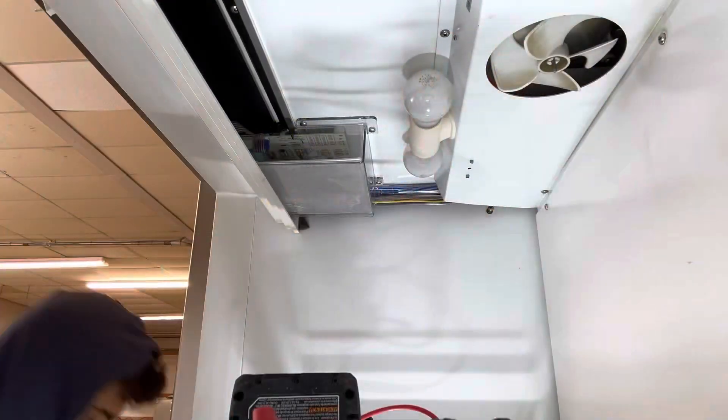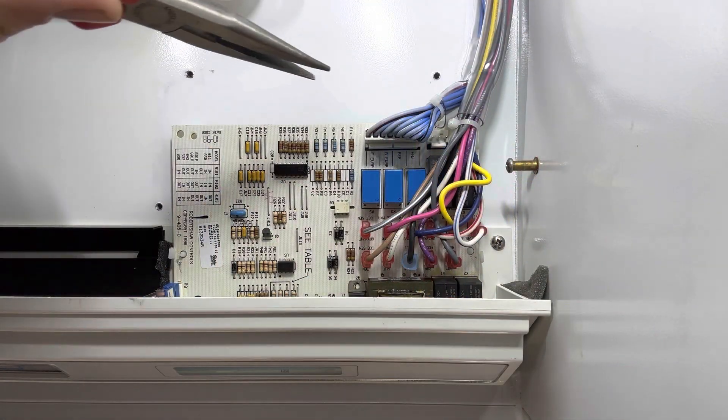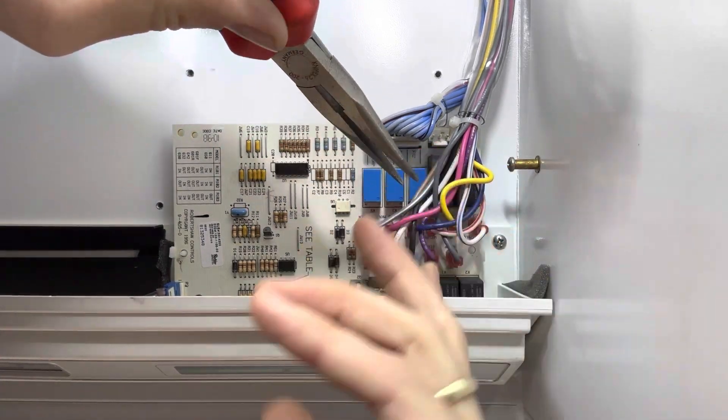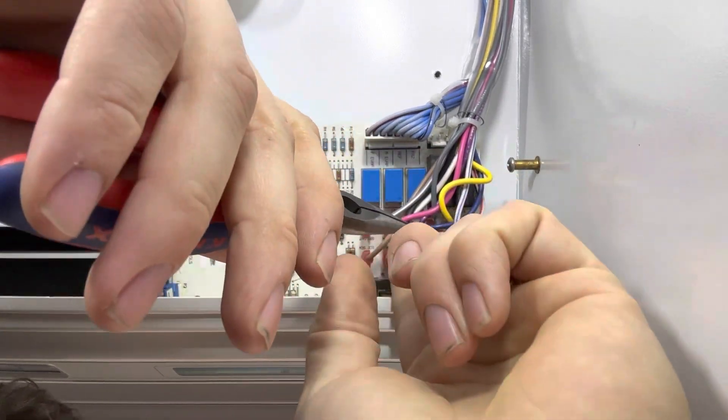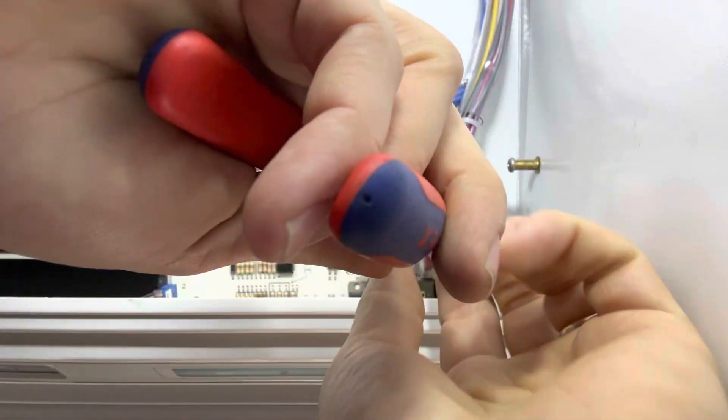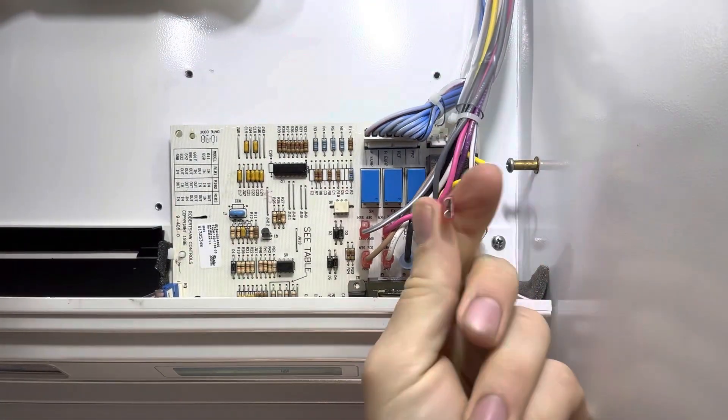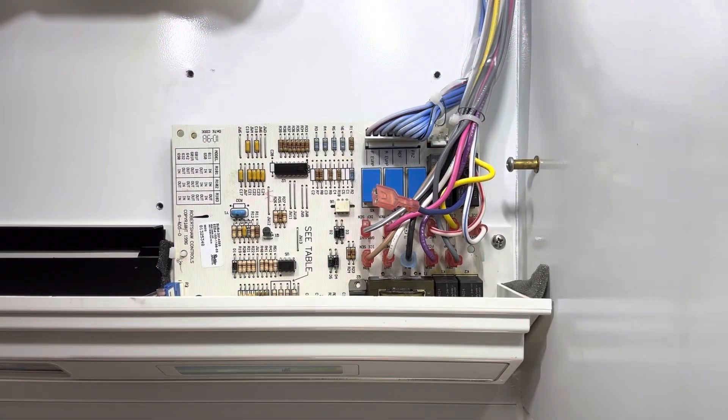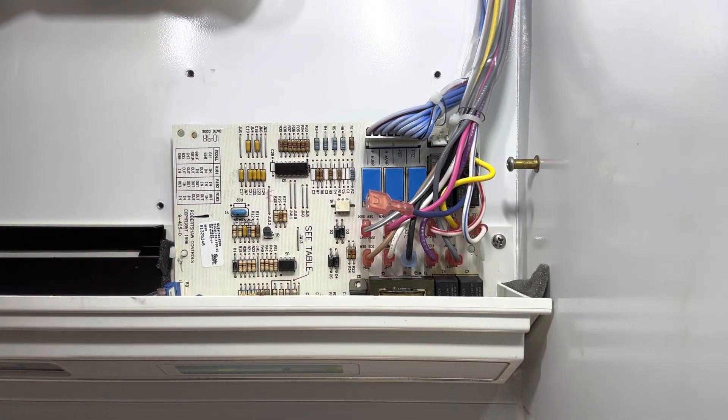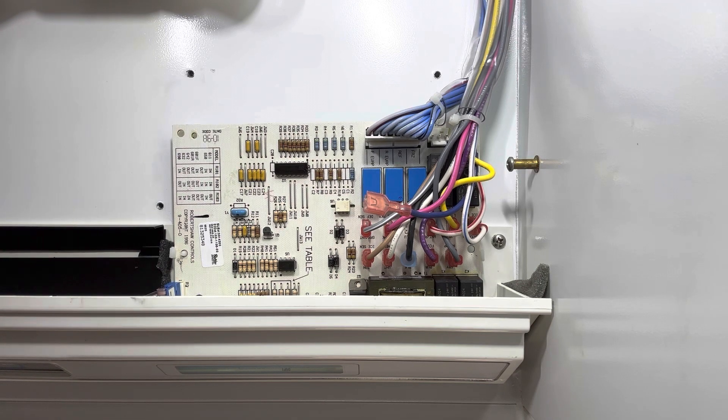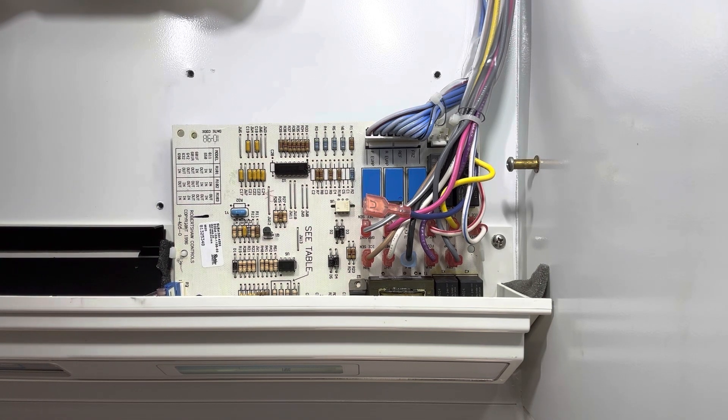Let's unplug the machine at the wall, and we're going to find the control board cover and remove the cover, exposing the control board. The next step, once we expose the control board—there is no power going through the machine right now—we are going to remove that blue wire for the defrost heater from its terminal. I use a needle nose plier and take the wire off. I'm going to restore power to this unit now, and we're going to go into a defrost mode. We're going to take our probes on our volt meter and take an AC reading at the terminal on the control board.